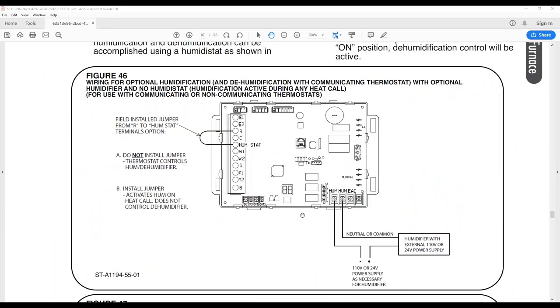So humidification, dehumidification. The first figure here is for communicating and non-communicating thermostats. You're going to notice there is a jumper from R to HumStat. This is on the thermostat terminals on the control board of the 96 variable speed. They call out some options here: A, do not install the jumper. That's when the thermostat is controlling the humidity or dehumidification. Do not install the jumper. Or B, if the thermostat is not controlling it, then install the jumper. When you install this jumper, it'll automatically energize those contacts and close them on a call for heat.